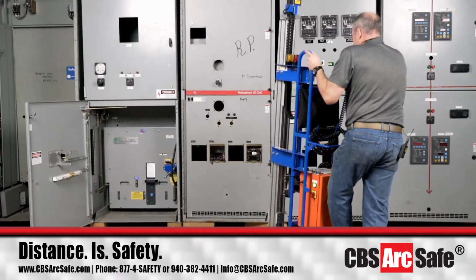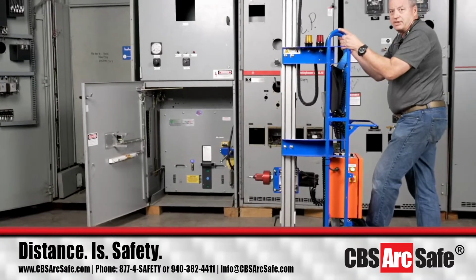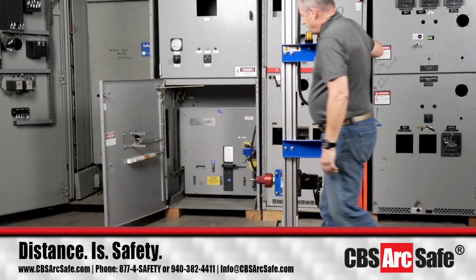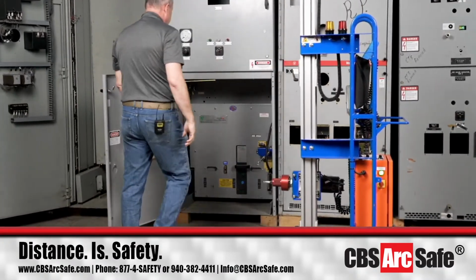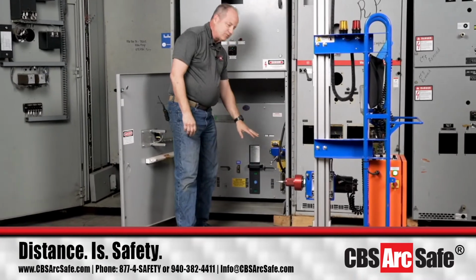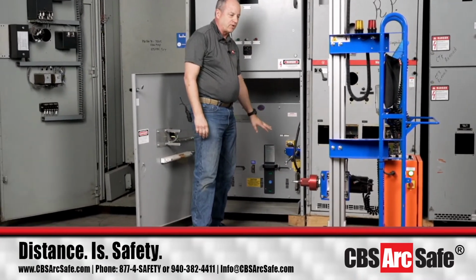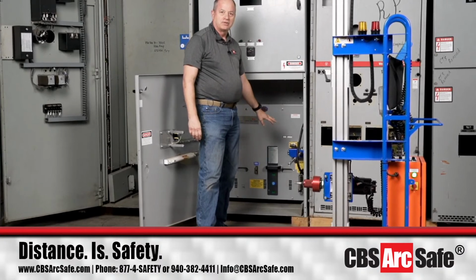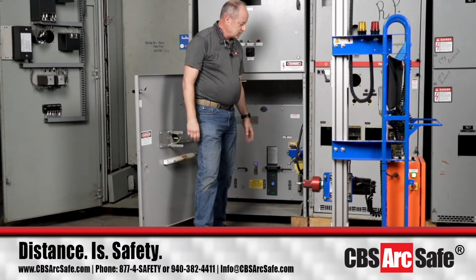So the first two breakers we used our foot latches on. This breaker, we've actually got a tetherless tool in here. We've got a magnetic tool because the unit's going to walk back and forth with the circuit breaker. We aren't going to put the foot latches on this time to rack the breaker in and out.